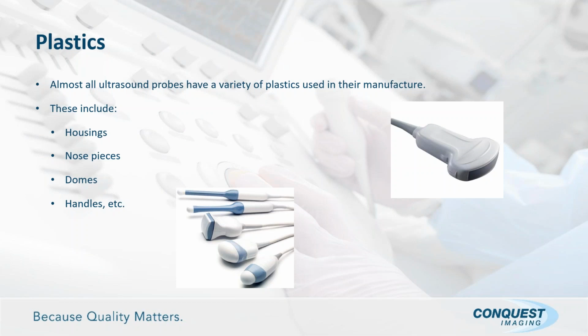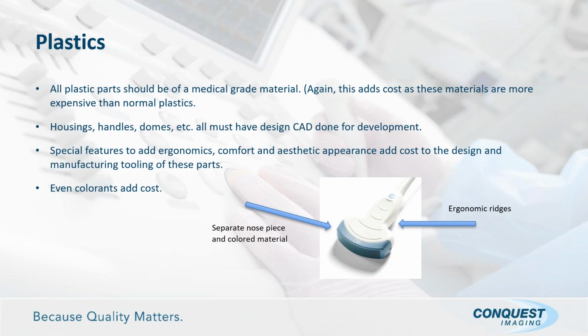Plastics, fairly straightforward. Again, probes use a variety of plastics. The outer housings, even nose pieces, domes, handles for the locking mechanisms, etc. Now, one of the things, again, the plastic materials need to be of medical grade. They need to be biocompatible. One of the things that the manufacturers know, and I know from a repair standpoint, is that as soon as you say medical grade to a materials manufacturer or supplier, their eyes light up because the price goes way up. And they're much more expensive than standard plastic. But again, we all know what industry we're in and what we're using them for. But again, it just adds a cost.